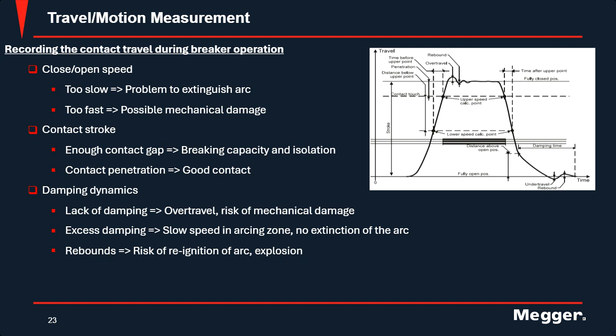So here's a few examples. For your close open speed, if it's too slow, it could be problematic extinguishing that arc. The longer that arc persists, the more your contacts are going to get burnt up, which is going to require you to do replacements. If it's too fast, you could end up damaging the mechanical structure of your operating mechanism. And then you have stuff like dampening dynamics. If you lack any dampening, you can have overtravel, which is mechanical damage again. If it's excess dampening or slow speed in the arcing zone, no extinction of that arc, like I said, and that could lead to further and faster breakdown of your contacts.